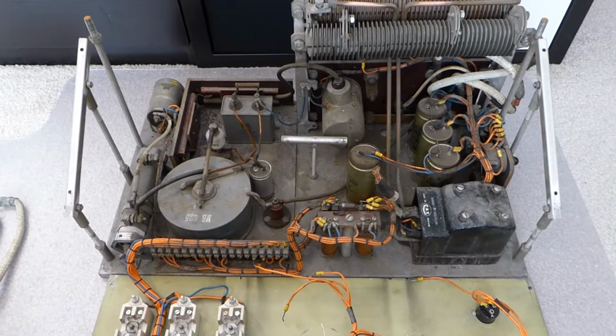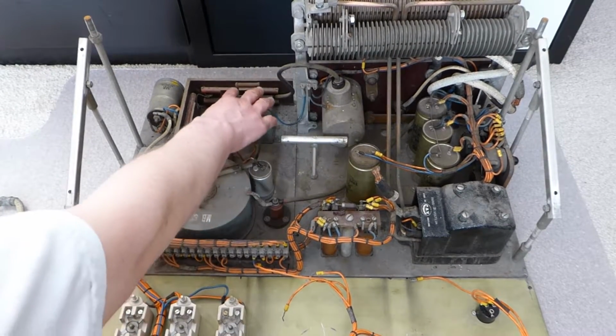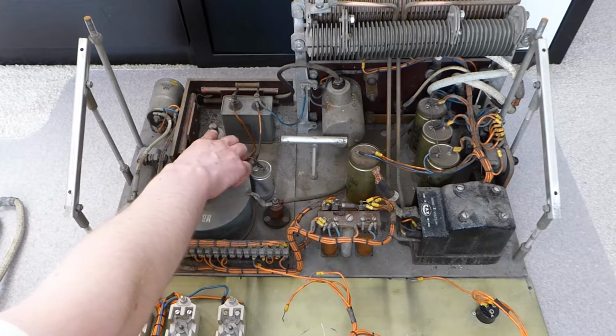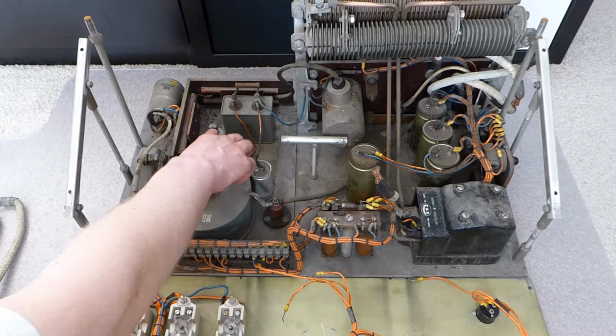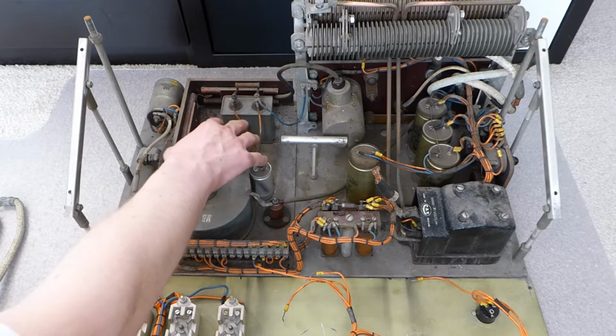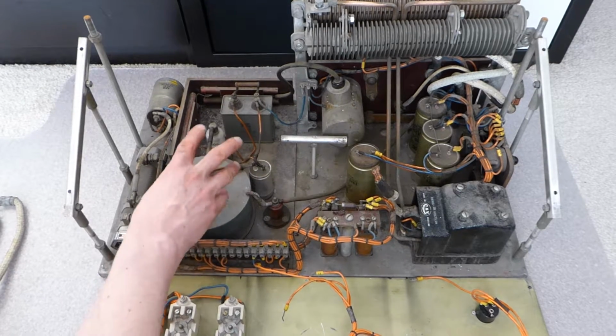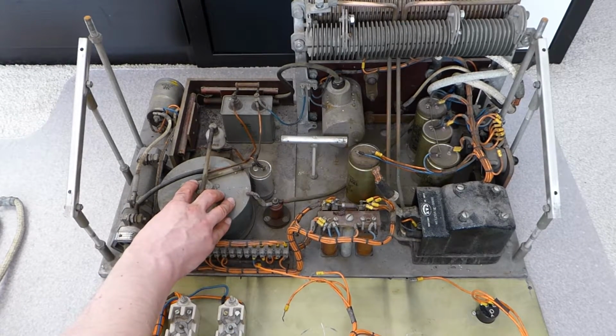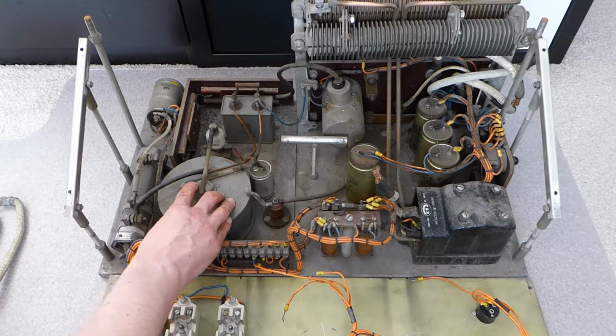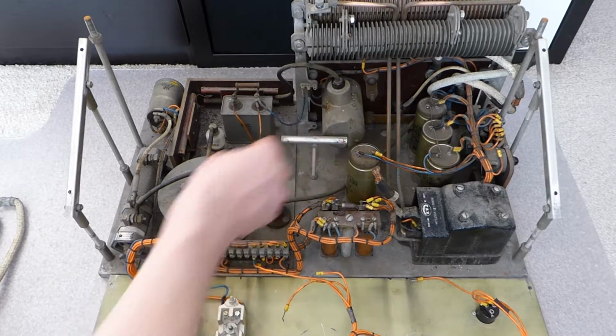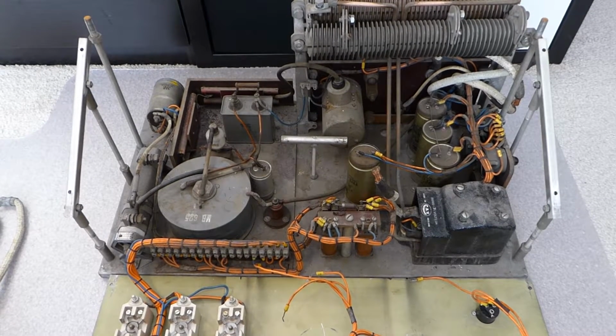The way that works is that as the capacitor charges up, at some point the spark gap will break down, which means you get a very large current pulse through the primary of this transformer, and that current pulse then induces a very high voltage in the secondary of the transformer, which goes straight out to the connector for the auxiliary electrode.